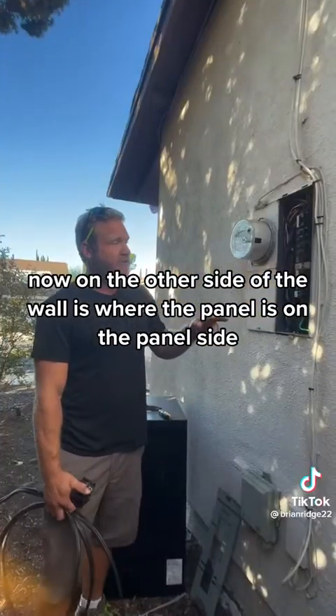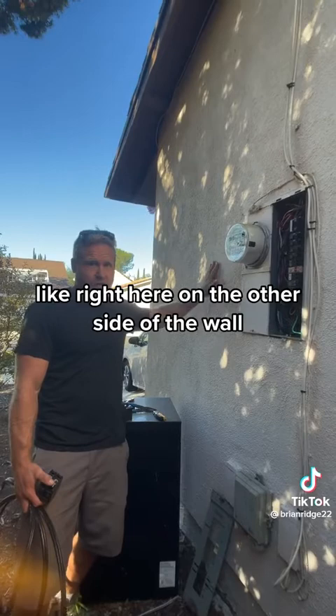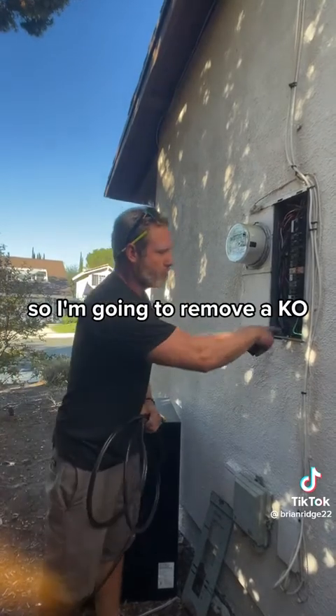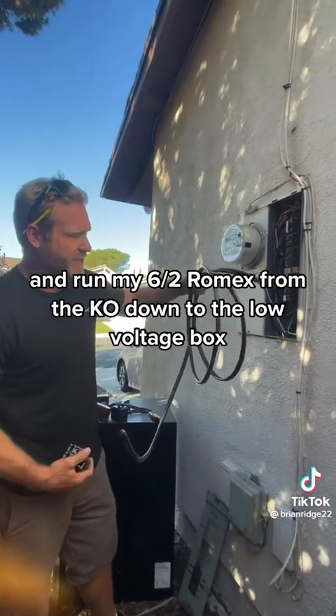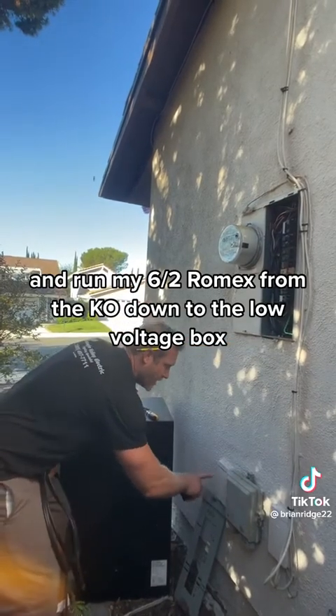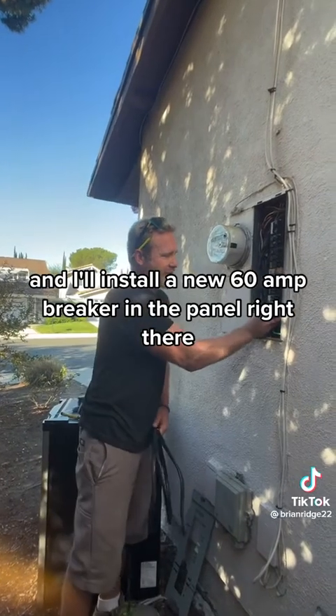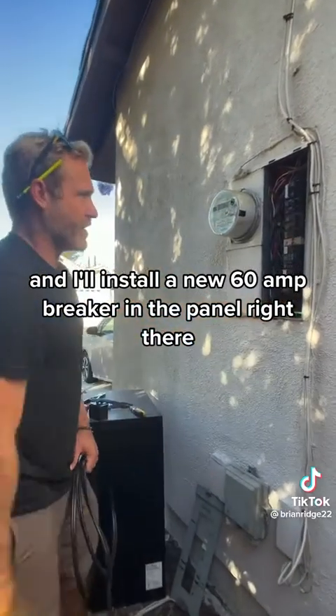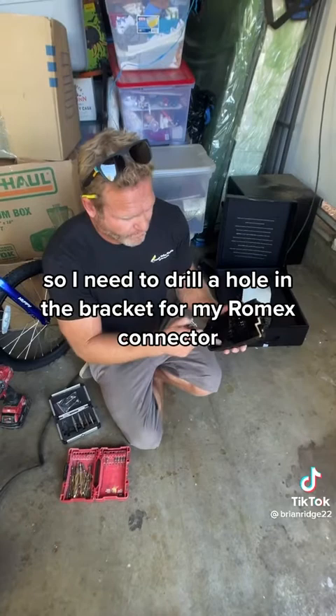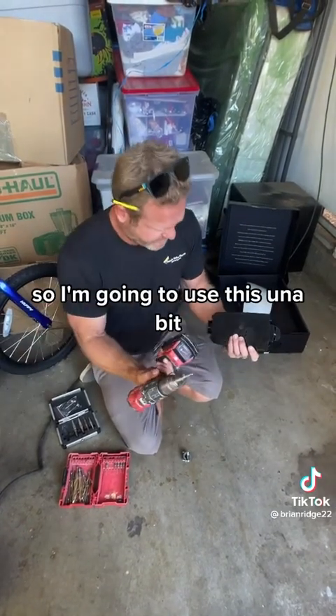On the other side of the wall is where the panel is. The wall connector is going to be installed approximately right here on the other side of the wall, so I'm going to remove a KO and run my 6-2 Romex from the KO down to the low voltage box and then up to my unit. I'll install a new 60 amp breaker in the panel right there. I need to drill a hole in the bracket for my Romex connector where the wire comes in, so I'm going to use this Unibit.